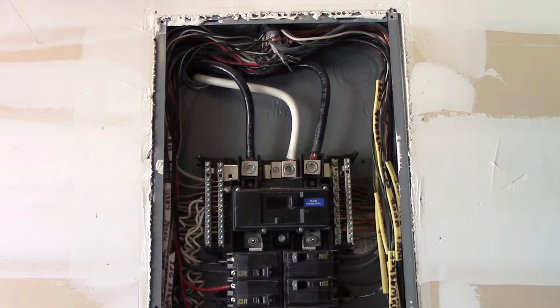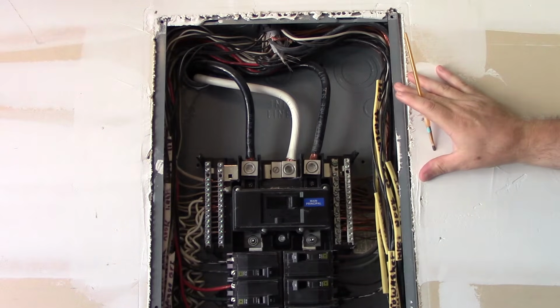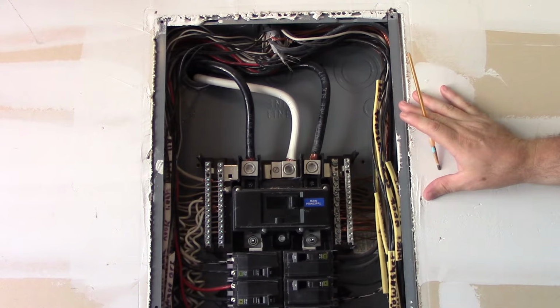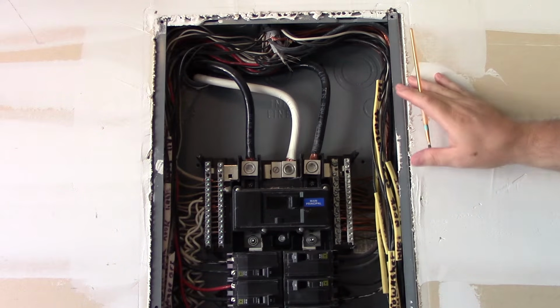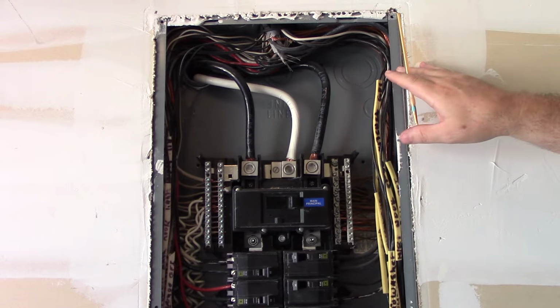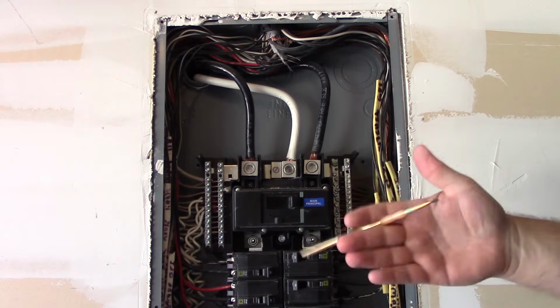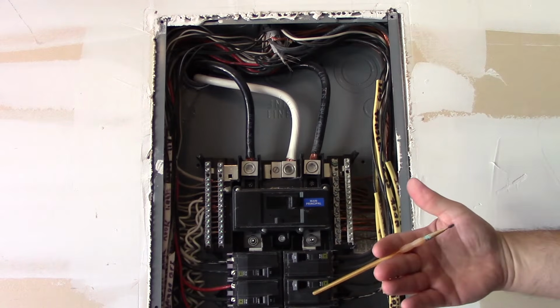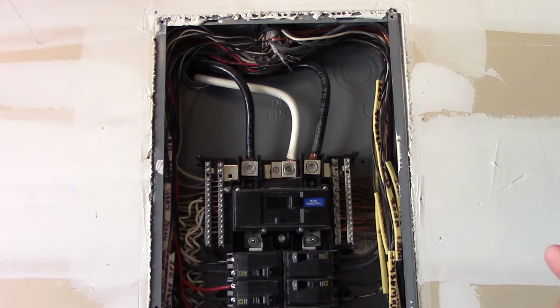All right, so let's start looking at this panel and seeing what we can notice here. The first thing I'm going to do as a municipal inspector, let's say it's a rough-in. If this panel is installed in a rough-in and I'm a municipal inspector, the first thing I'm going to look at and see is, is this material around it actually combustible or not? And here it's a gypsum board or drywall, however you want to call it, and it is non-combustible. So I know that this enclosure can be installed at up to 1/4 of an inch back into the wall, recessed into the wall. Now that's in accordance with 312.3 of the National Electrical Code.